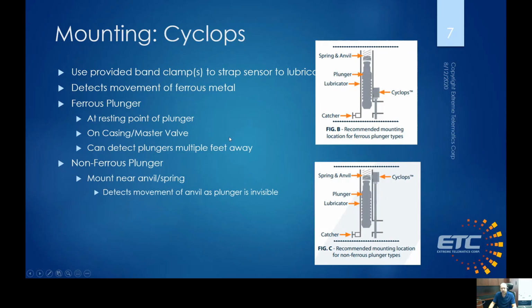Now, if you're using a non-ferrous plunger, what you want to do is mount it near the anvil or spring up here, because that will be a ferrous piece of metal, and the plunger itself will be invisible. So if you're using aluminum or titanium or stainless steel, you actually won't pick up the plunger. You'll pick up movement of the well components. The only time when that isn't the case is if the manufacturer of the plunger has put in magnets or other ferrous materials for the Cyclops to be able to trigger on.